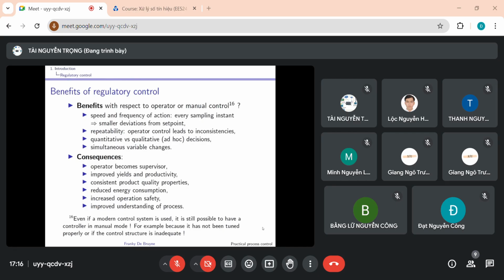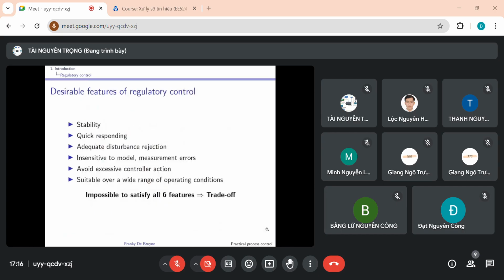You might wonder why we are comparing process control in automatic mode with process control in manual mode. Well, even in a modern control system, manual mode might be encountered often. Manual mode, except in certain situations such as production startup, is often indicative of a problematic situation. For example, a control that is not tuned properly, a control structure that is not adequate. And what happens is that the operator does not have confidence in the control action and takes the controller to manual mode.